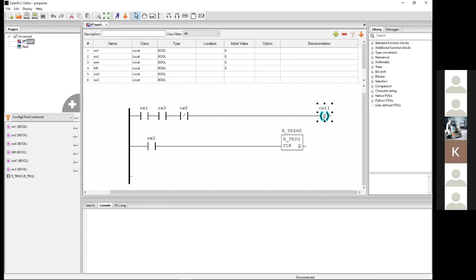The coil can either be dynamic, or it can be set or reset. You can see I put 'yes' here, which means it is set — once the logic is triggered, the output is set and stays in the same state forever, until we disconnect and reconnect the power or do a reset some other way. But if you'd like the output to be dynamic, then if the logic is executed, the output will be high, and if the logic is not met, the output will be low. So it's a dynamic one.